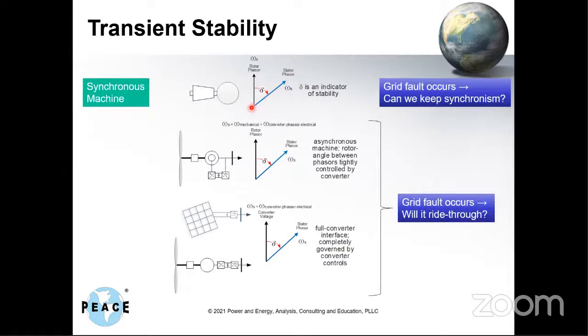So you could think of this as the grid phasor, and this is the rotor phasor. And obviously this angle between the two is the indicator of stability, right? We all know the classic equations that if this angle goes beyond 90 degrees, then we lose stability. And if this thing oscillates, and doesn't have damping, it can go unstable. Well, all those things are controlled by the excitation system and the turbine governor, right? So the excitation system gives us this synchronizing torque, which allows this angle to quickly come back into synchronism. We have a power system stabilizer to stabilize the oscillations. And then we have a turbine governor with primary frequency control to regulate frequency and keep the balance between active power and load.